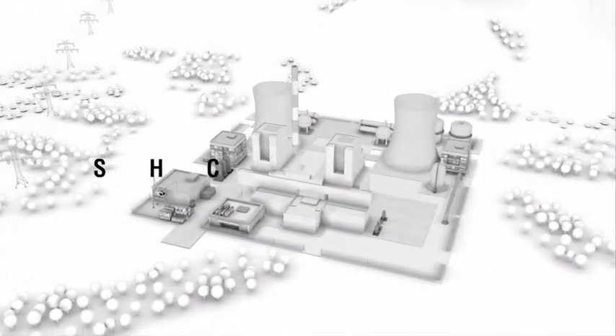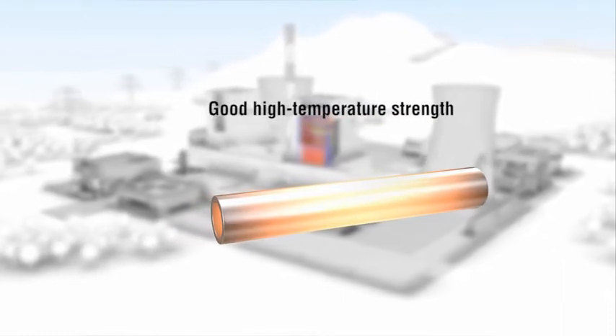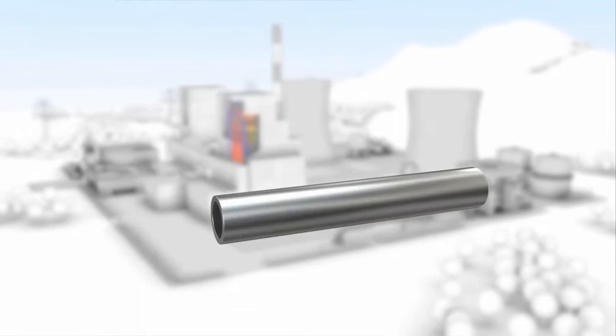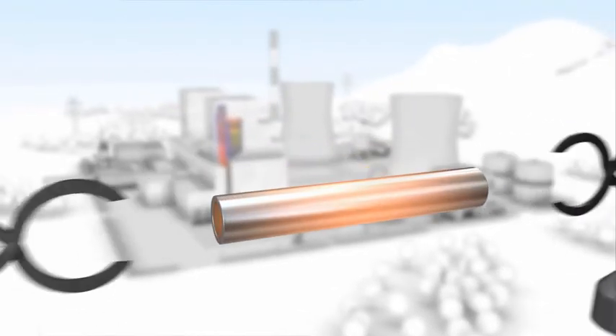Modern power plants nowadays are operating under temperatures beyond 600 degrees centigrade. Due to this fact, the high-temperature corrosion and the creep behavior of normal ferritic materials mean these are not possible to be used. The VM-12 SHC contains 12% chromium, which provides both the necessary oxidation resistance and the creep rupture strength values. Very important, of course, is that the steel maker recommendations have to be followed during processing of the VM-12. Following these recommendations, no problems will occur because this material is very similar in handling to the P-91 material, which is well known on the market.